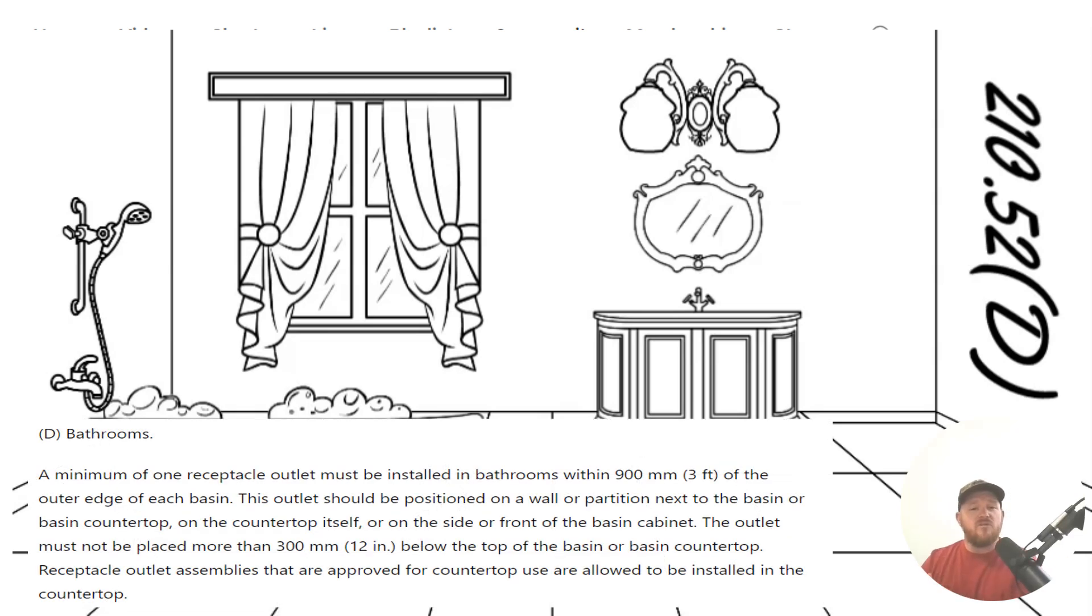A minimum of one receptacle outlet must be installed in bathrooms within three feet of the outer edge of each basin. The outlet should be positioned on a wall or partition that is next to the basin, or basin countertop, or on the countertop itself, or on the side or front of the basin cabinet. Now let's stop right there, and then we'll finish reading it here in just a moment.